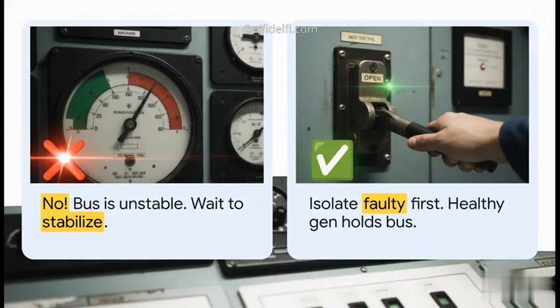Conversely, for loss of excitation, you actually don't desperately need to take another generator on load immediately. The healthy generator is already holding the bus. Your pathway here is swift isolation. You want to open the breaker of the faulty set promptly, letting the healthy machine take the full load safely.